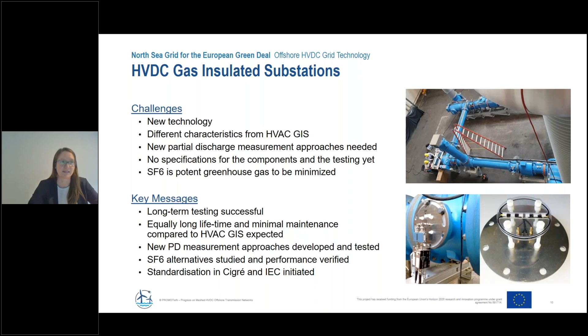Within this work, there was successful long-term testing, and we expect an equally long lifetime and minimum maintenance compared to HVAC GIS. New partial discharge measurement approaches were developed and tested, shown here on the right, and SF6 alternative gases were studied and verified. All of this work was then contributed to standardization in CIGRE and IEC bodies.